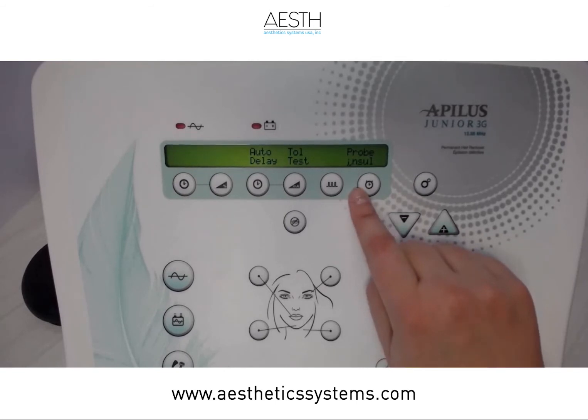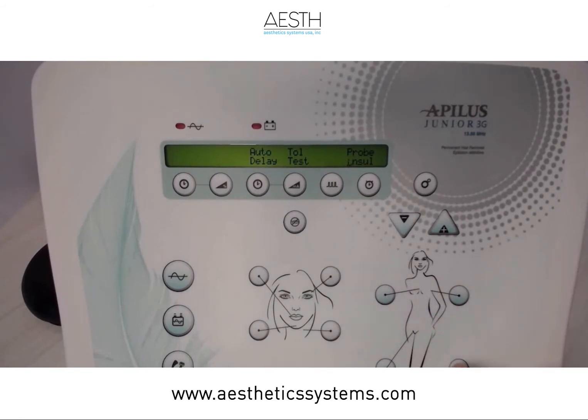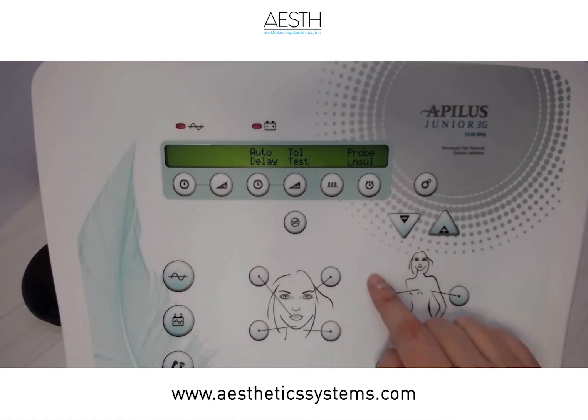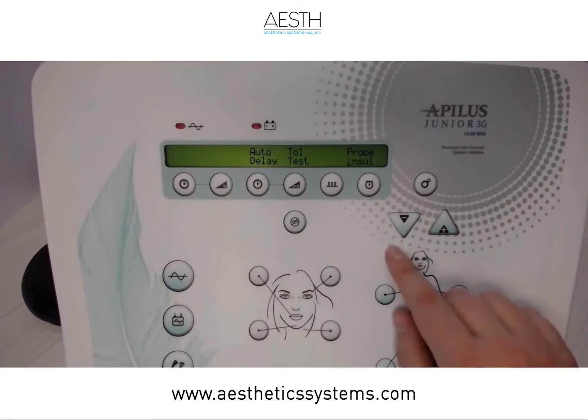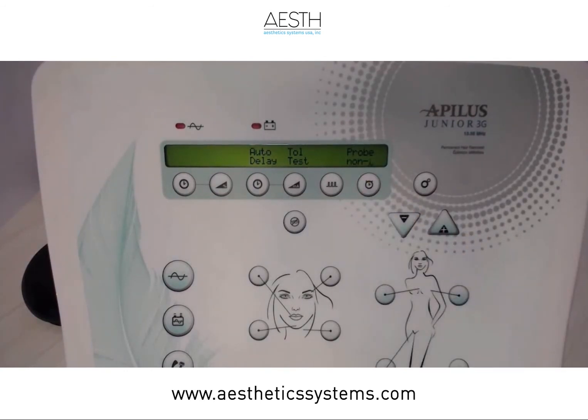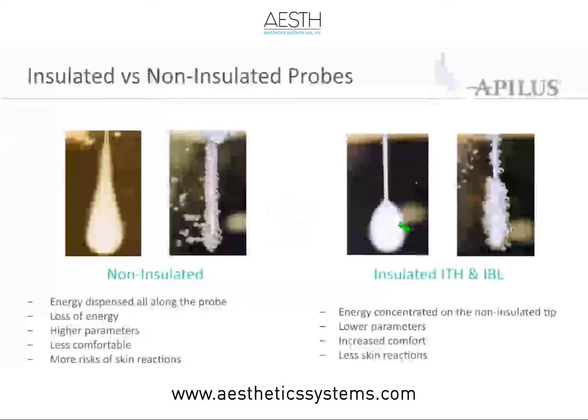Essentially what this means is that if I have, for example, a preset, let's say I'm using leg and I'm using level 4. If I'm using leg in level 4 with insulated settings, the time and the intensity will be less than if I used leg 4 with non-insulated settings. The reason why this is even an option on the machines is because we take into account that with non-insulated probes, you have a lot of loss of energy higher up in the probe where you would see Teflon coating or some sort of insulation on insulated probes. This means that with the loss of power, you naturally need higher parameters. Because you need higher parameters, everything is just going to be a little bit higher with the non-insulated presets.